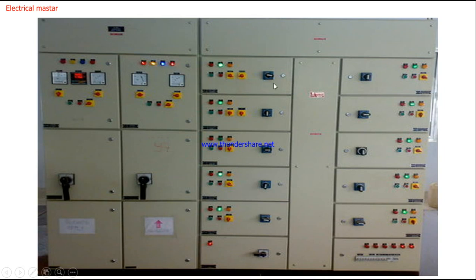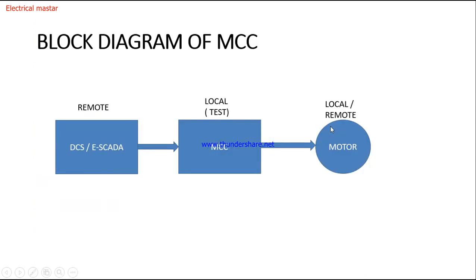This cubicle has the power main and control supply to turn on the power supply for the motor. There is one isolator for on/off. You can see the indications for motor start, stop, and also trip. There is a local test pushbutton, an emergency stop, and also a selector switch for the motor for local or remote operation. So this is the basic idea of the MCC panel. Now we will see how to read the schematic diagram.